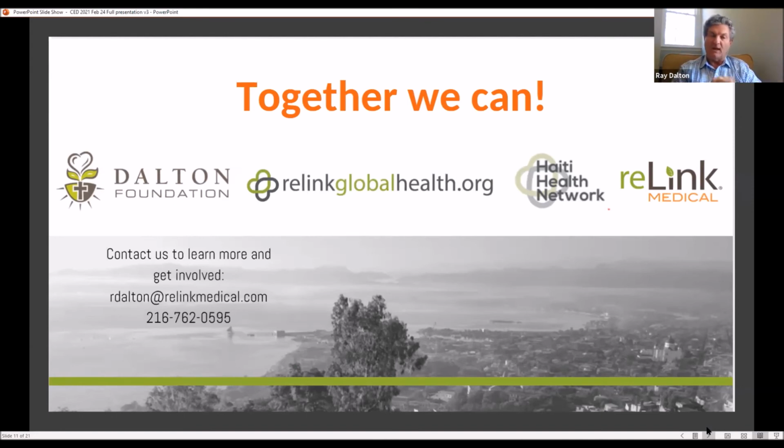What COVID proved to us in Haiti and Malawi and other countries we're working in, it's the problem was still there. It just accelerated the need to solve it more quickly and more focused. So instead of taking a global approach about, hey, what do we have in the building? It's what are these 7 or 8 devices? What is the status of those? And they must work now. They became hyper-focused on respiratory working and anesthesia working and pulse oximetry working. And so it gave us the opportunity to really say, if we're going to bring more equipment in, the junk has to come out. And that's one of the conditions of being a partner.